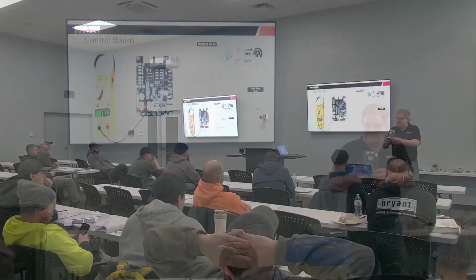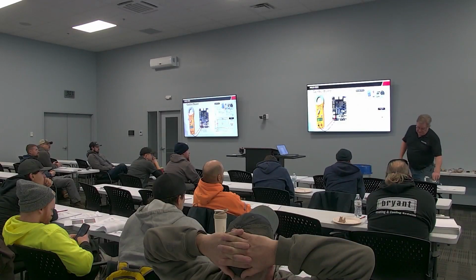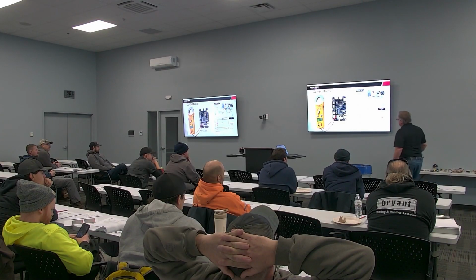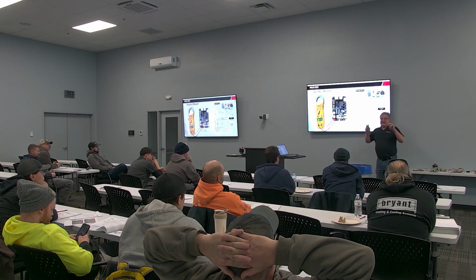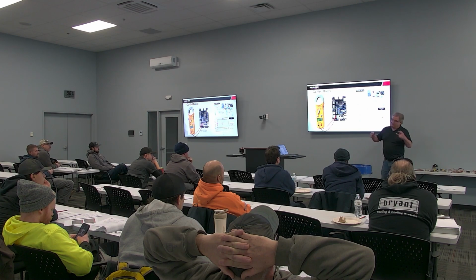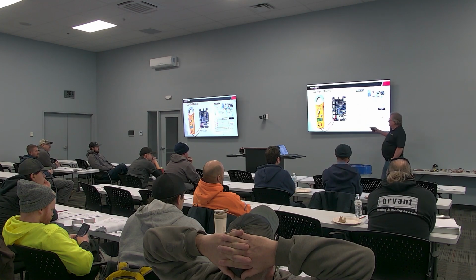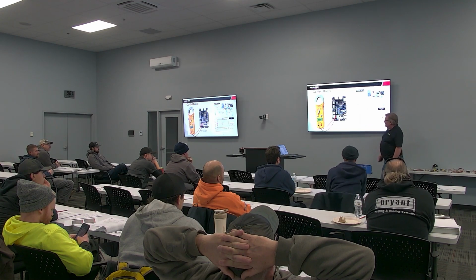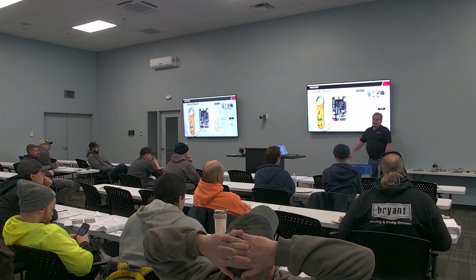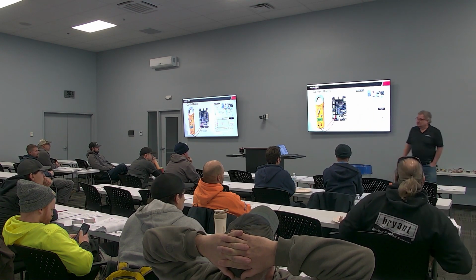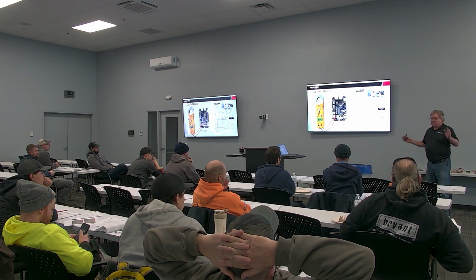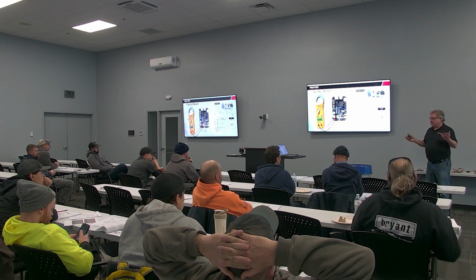Now, we do not just crank this thing up all the way because you're going to end up with blower problems. So now what I'm going to do, the blower does not need to be running. The unit just needs to be powered on. So I don't want the blower running to do this. I need the blower running for the static, but not to set this. Power on, I'm going to turn this dial until I get 9 volts DC on my meter. Okay, the blower is set up. Okay, that's all I got to do.